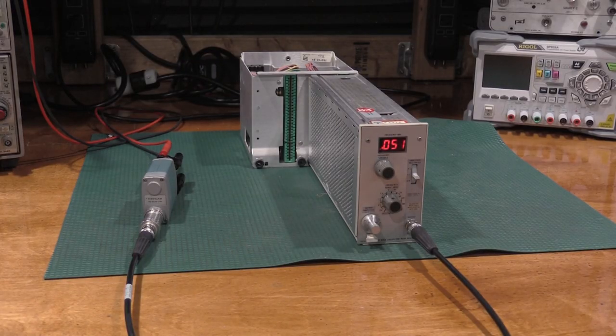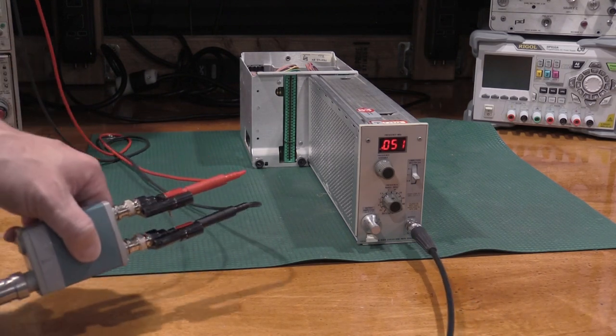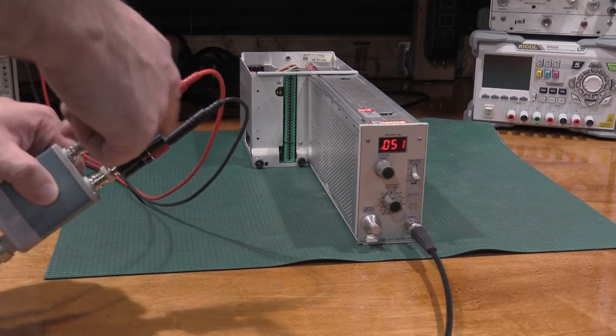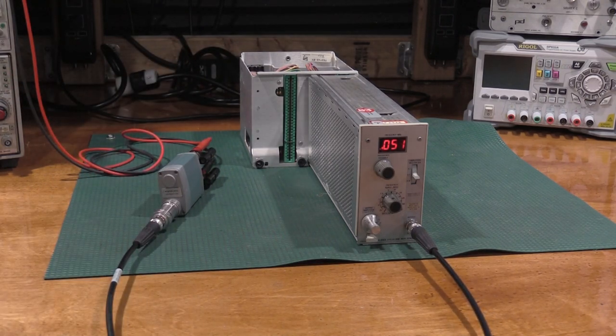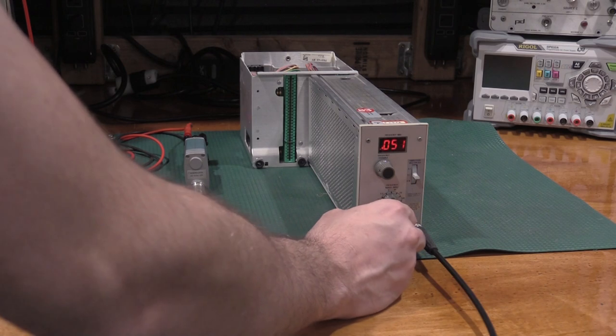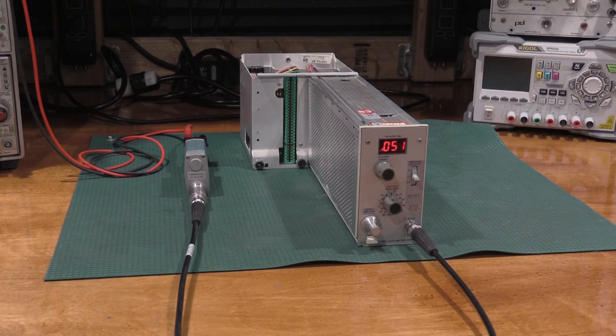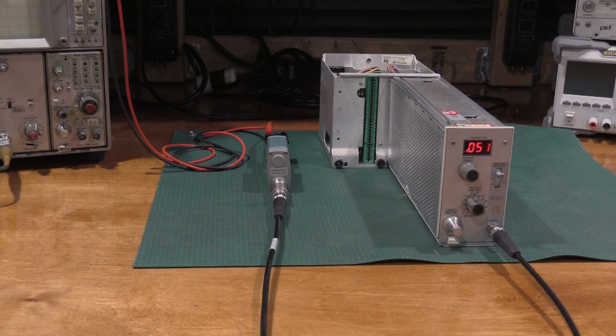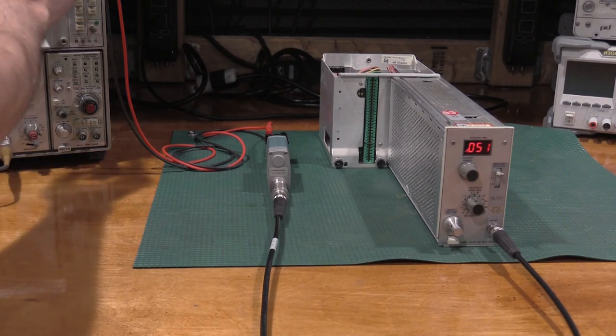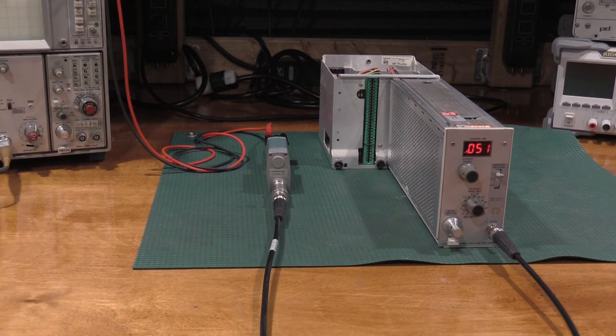Okay. I'm ready to check the last step of the SG503. I've got the precision BNC cable hooked up to the peak-to-peak detector. I've got this contraption that they wanted me to build, which is the positive and negative with a 2.4 megaohm resistor between the two coming out into the DMM 7510. I have everything dialed in pretty good. Now I just have to sweep the ranges and make sure. To check the flatness up to between 50 megahertz and 100 megahertz, I've got everything set up. I'm actually going to change the meter a little bit to make this easier, because we're going to go relative measurements.